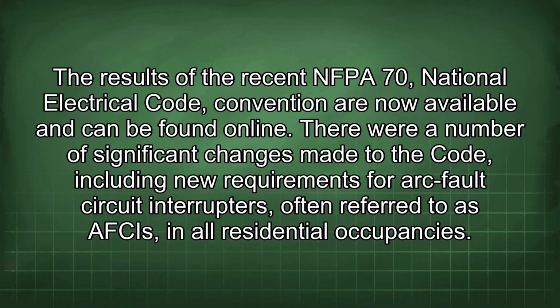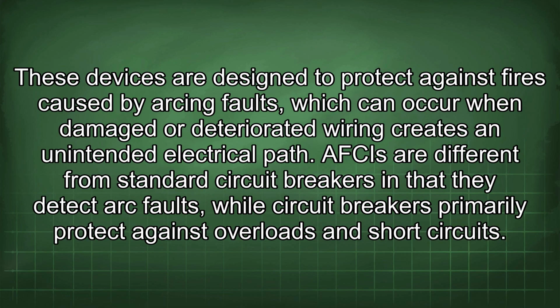The results of the recent NFPA 70 National Electrical Code Convention are now available and can be found online. There were a number of significant changes made to the code, including new requirements for arc fault circuit interrupters, often referred to as AFCIs, in all residential occupancies. These devices are designed to protect against fires caused by arcing faults, which can occur when damaged or deteriorated wiring creates an unintended electrical path.